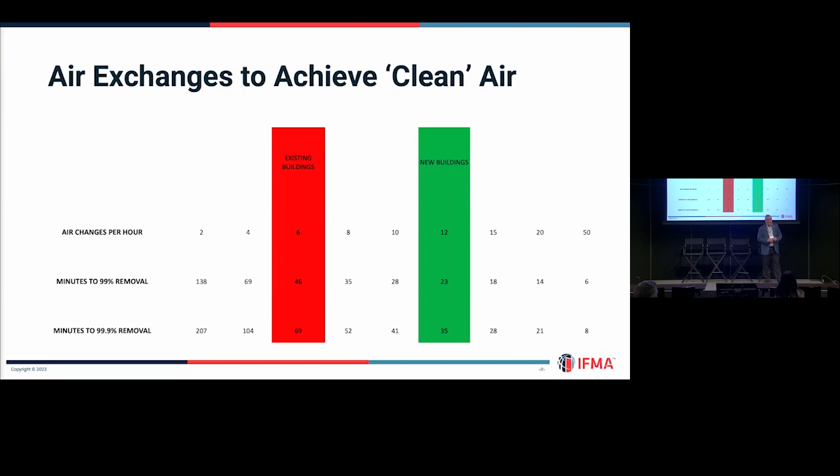Yeah, it was a booger a couple of years ago when we had all those fires because we were in the middle of COVID as well. CDC said, open up your outdoor air, 100% outdoor air, bring it in, flush everything out of your building. Great, now I'm bringing in smoke and particulate and all of that stuff. And like Bobby said, I can't go put MERV 11s or MERV 13s on my system. It'll kill it. So what do?